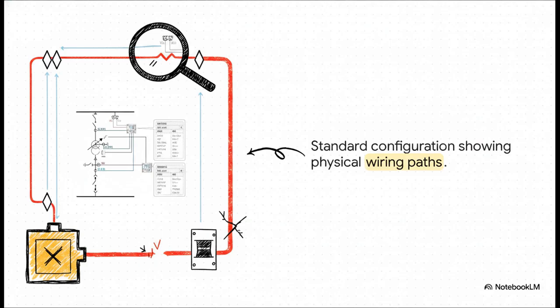So this brings up a really crucial concept: the physical separation between our smart protection relay and the actual heavy-duty breaker hardware. People often just assume that if a relay's front panel looks healthy, if its internal self-diagnostics are flashing green, then the whole protection chain is secure. But look closely at the standard configuration. Notice that distinct external wiring path running out to the breaker trip coil? The relay's internal software is completely blind to the fact that this external copper wire might have degraded, or say a connection wiggled loose over time.